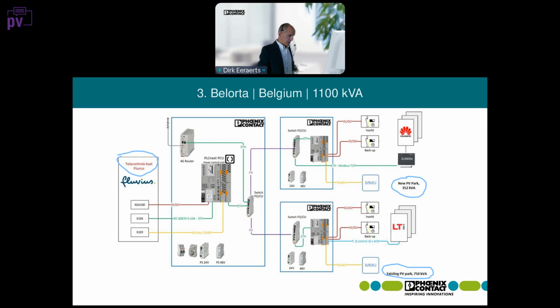So here you see that with this DSO we communicate over protocol 104. We receive the control signals, we also receive statuses, and the Modbus connection is actually used to send back meter values from the 2 fields. Measurements come in and are sent back to the RTU of the DSO in this case.